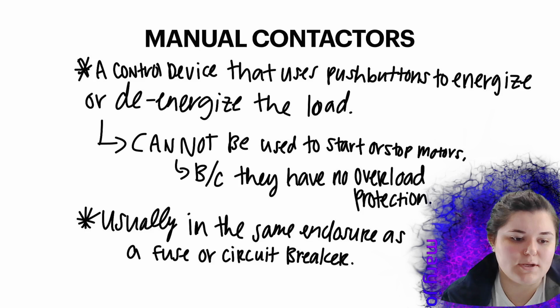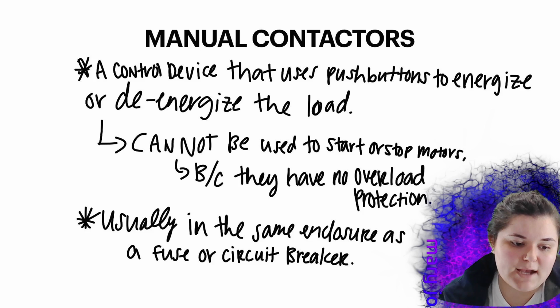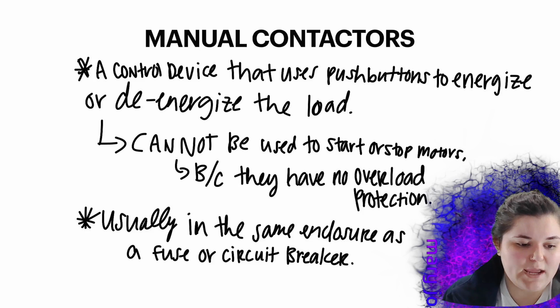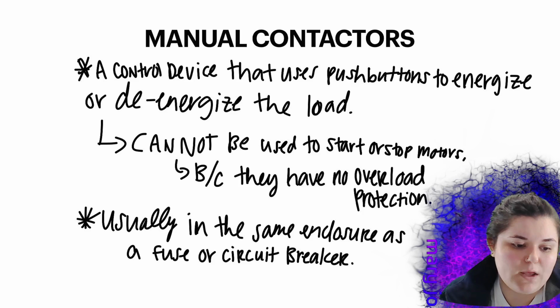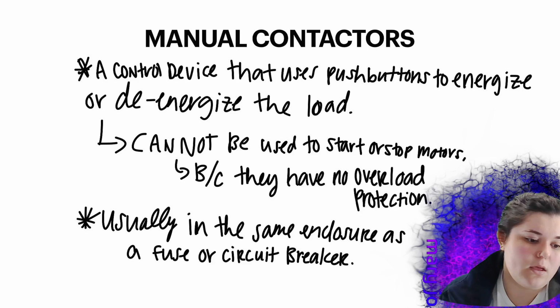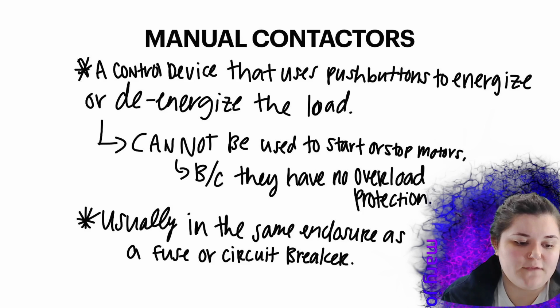So manual contactors. That's a control device that uses push buttons to energize or de-energize the load. Cannot be used to start or stop motors because they have no overload protection. So a manual contactor cannot start or stop a load or a motor. Usually in the same enclosure as a fuse or circuit breaker.